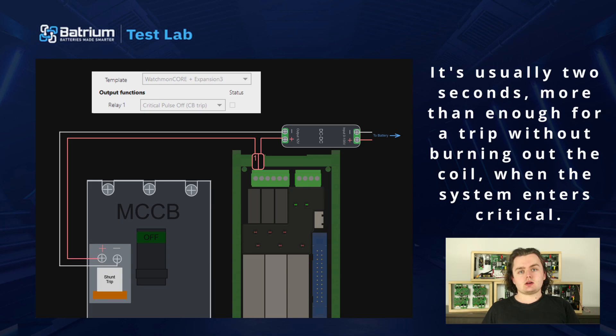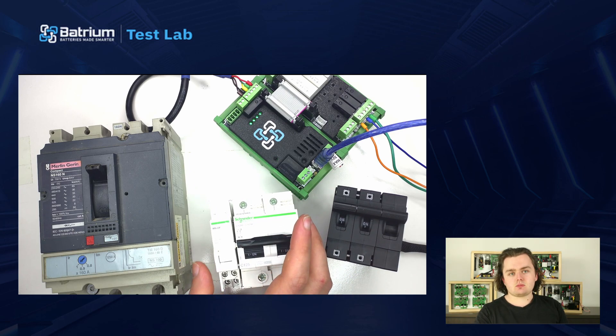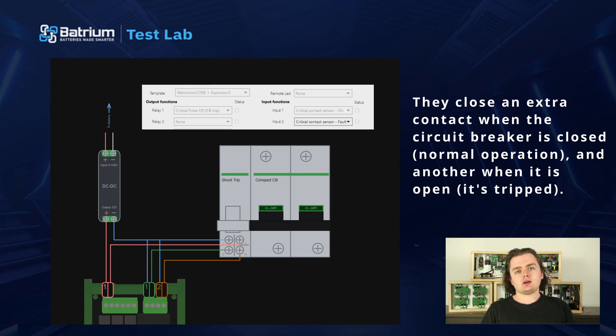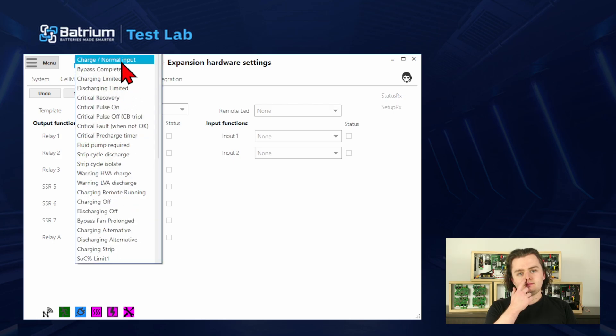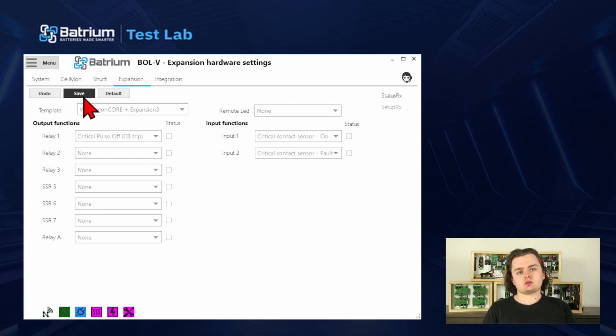The next scenario is a shunt trip with feedback. These are common on the smaller circuit breakers like the one we've got here — the shunt trip sits off to the side and snaps on. It's basically the same as the last one, the only difference is that they close an extra contact when the circuit breaker is closed in normal operation, and another one when it's open and it's been tripped. These extra outputs can be wired into the inputs on our expansion board to check the state of the circuit breaker, so the BMS knows if a short caused it to trip or if the shunt trip failed and needs to be triggered again. Here's how you would configure that in our software and here's how you might wire that up. Just make sure to check your specific shunt trip instructions to find out which pin is which, because they're all a bit different.